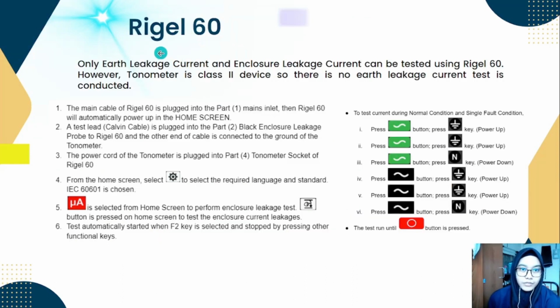Next one, we use the Rigel 60. Only earth leakage current and enclosure leakage current can be tested using the Rigel 60. However, because the tonometer is a class 2 device, there is no earth leakage current test conducted. So for the procedure, first, the main cable of the Rigel 60 is plugged into the part 1 main inlet, and then the Rigel 60 will automatically power up to the home screen.